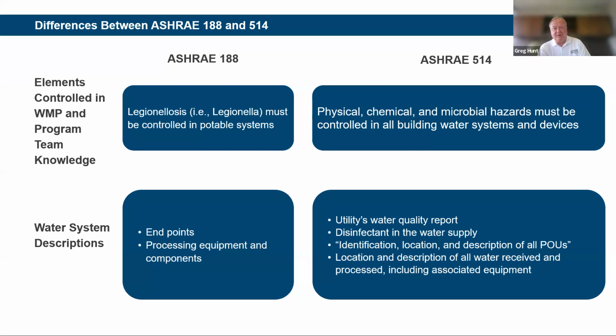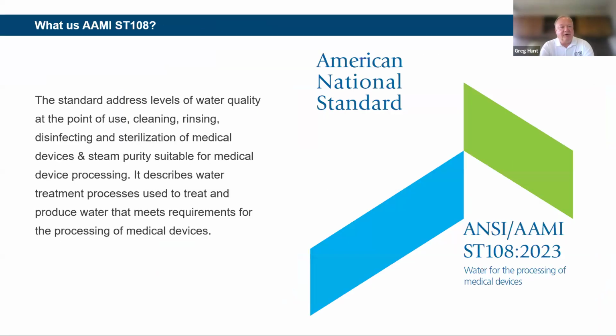Thanks, Spencer. I think this next slide on ST 108 is also going to be very interesting to this audience. This is one of the newest standards we've been seeing facilities incorporate into their water management program. This is AAMI ST 108, and it's focused on the water for processing of medical devices. It addresses water quality at the point of use, cleaning, rinsing, disinfecting and sterilization of medical devices, and the steam used for medical device reprocessing.